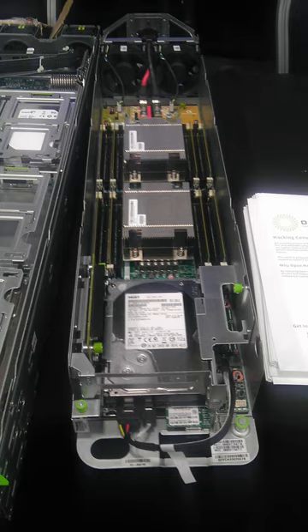Data center designs for energy efficiency include 277 VAC power distribution that eliminates one transformer stage in typical data centers. A single voltage, 12.5 VDC, power supply designed to work with 277 VAC input and 48 VDC battery backup.